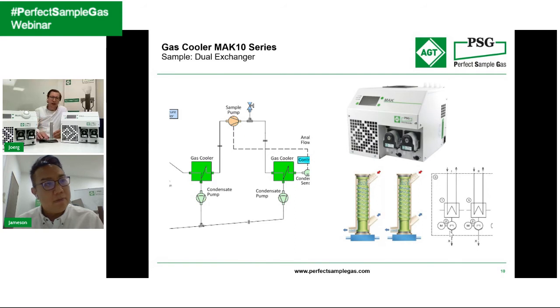So you would say this is a backup kind of thing. Technically or theoretically, if the first heat exchanger would do a perfect job, whatever a perfect job is, there would not be a need for a second heat exchanger, but you would always recommend having it just to make sure it's really dry afterwards, right? Yes. Because after all, you're investing in a gas cooler. Why not just add a couple of dollars or euros to add a second exchanger? It's much more expensive after commissioning, when you recognize that something happened and you have to attend to it. The man-hours and the trips cost you much more. For that reason, absolutely.